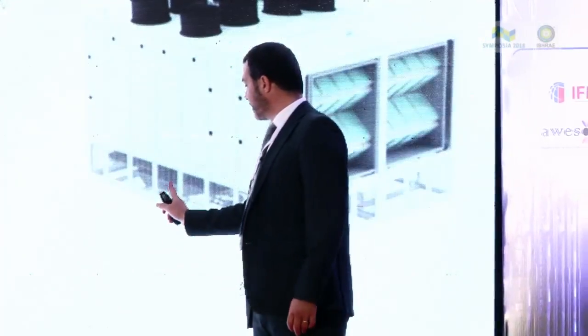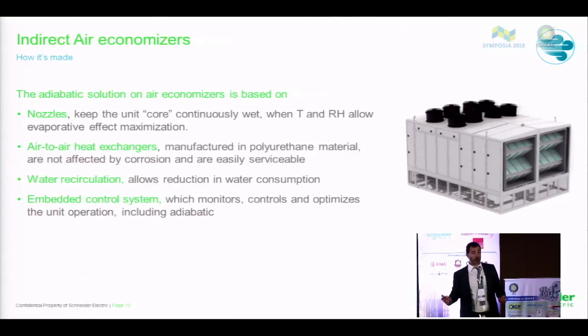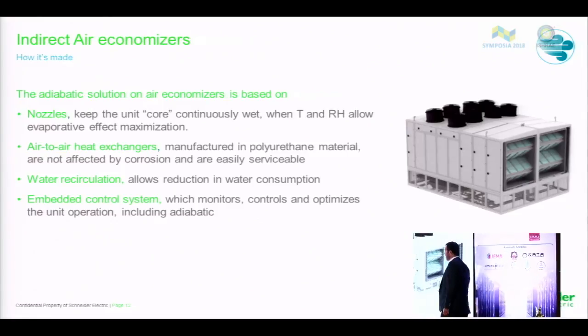In between here, there is an air-to-air heat exchanger that exchanges capacity with the external air. So the air from the data center passes through here. The air from outside enters here and passes through here. So without mixing the air, the internal air and the outdoor air are able to dissipate part of the load. Of course, this is enhanced by some spray, some nozzles over here that keep this heat exchanger wet. So there is a lot like a shower that keeps the heat exchanger externally wet, not internally, so not on the air that goes to the data center, but on the external air.